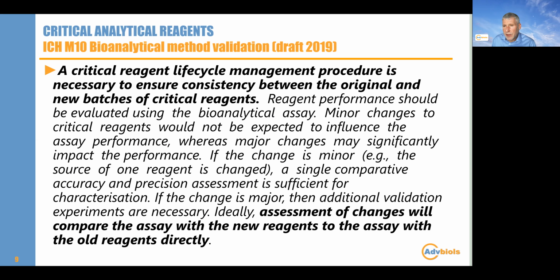So what you're trying to do is obviously maintain consistency of reagents over time. And you might be on the market for 20, 30 years, maybe more if you're lucky. And if you don't change the assay, then you're going to have an ongoing requirement to keep that assay performance up to scratch, which might mean things like trending of your analytical methods in the same way you do with your process. And it will be expected that you compare the existing batch of critical reagent with the new batch of critical reagent.